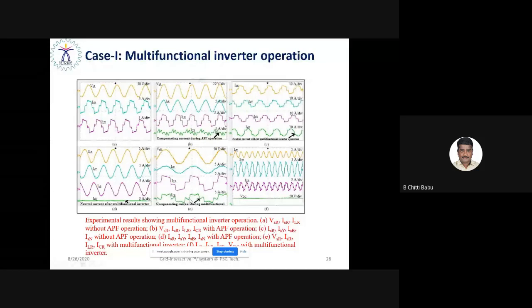You can see here, with the multifunctional inverter, the supply voltage and supply current. Still the load current is not sinusoidal. You can see the compensating current during multifunctional operation; it is still not sinusoidal. But moreover, with the multifunctional inverter, you can see the neutral current becomes zero.